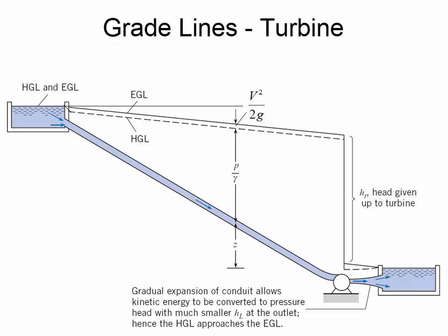All of the water pressure of this elevated reservoir, that pressure is sort of pushing the blades in the impeller. That's why the impeller turns, is because on the upstream face of the impeller is this really high pressure of a certain height of water. You've got all the pressure in this pipe because this tank is elevated. You lost a little bit of energy due to frictional losses through the pipe between the reservoir and the upstream face of the turbine, but still there's a lot of pressure in there before the turbine.